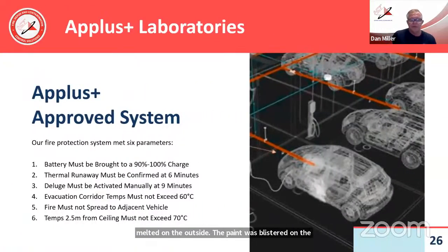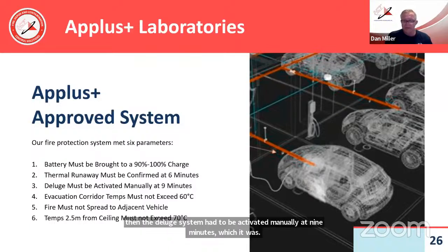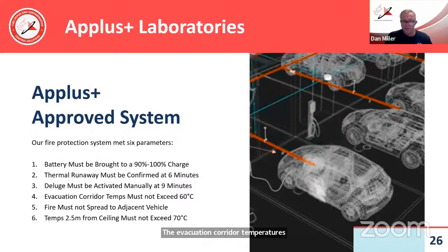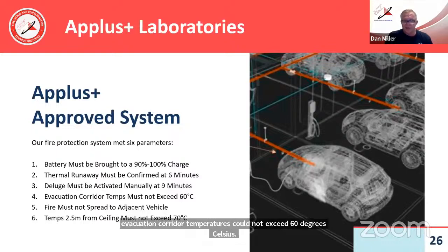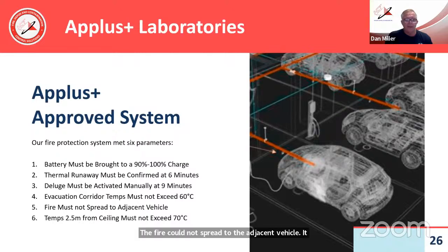So to meet approval, the fire protection system had to meet 6 parameters. The battery must be brought to a 90 to 100% state of charge, which it was. Thermal runaway had to be confirmed at 6 minutes, which it was. And then the deluge system had to be activated manually at 9 minutes, which it was. The evacuation corridor temperatures could not exceed 60 degrees Celsius, so survivable. The fire could not spread to the adjacent vehicle. It did not. And the temps at 2.5 meters down from the ceiling could not exceed 70 degrees Celsius.